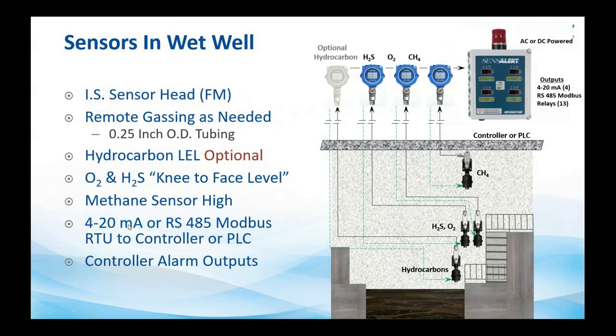Just one comment on communications. I'll cover this a little bit more when we talk about the products, but these all can have 4-20 milliamp output, they can have relay output, and then we can bring these back into a controller. So it can be a really standalone safety system as well. We also have our RS485 Modbus.